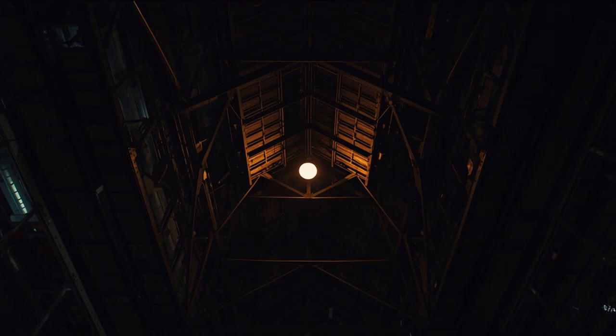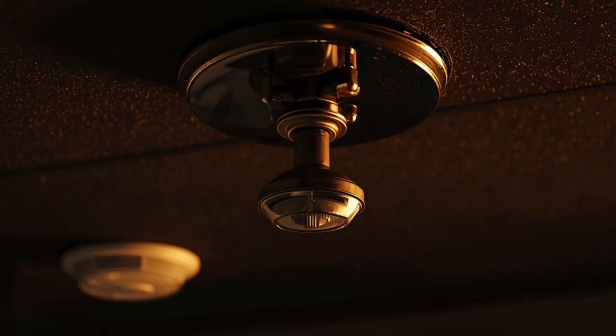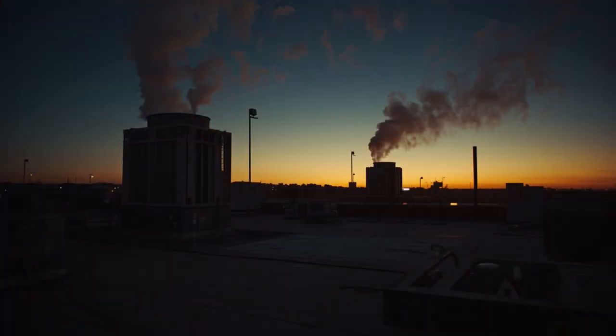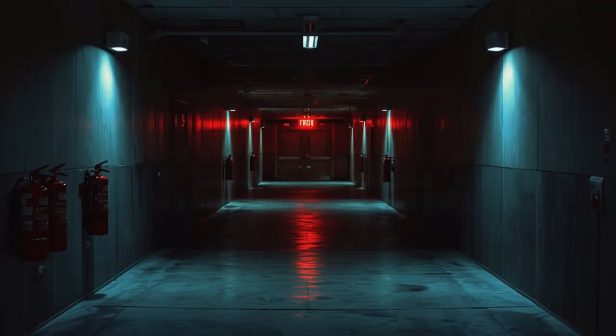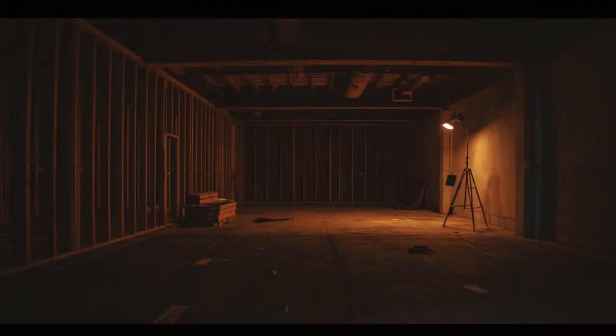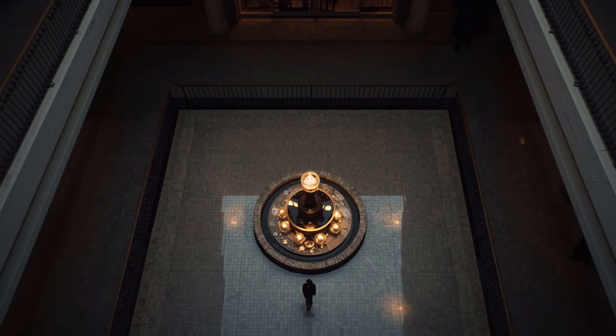In the mall atrium, the glazed roof covered a substantial area of the building's total envelope. In the summer, solar radiation passing through that glazing and converting to heat within the atrium could raise the interior temperature significantly above what the surrounding areas of the building experienced. In the winter, the relatively poor thermal resistance of even double-glazed units, compared to an insulated roof panel, meant that heat was lost through the atrium roof at a rate considerably higher than through the opaque portions of the envelope surrounding it. Both of these effects, summer heat gain and winter heat loss, had direct implications for the size, configuration, and operating cost of the mechanical systems responsible for maintaining comfortable conditions throughout the building.